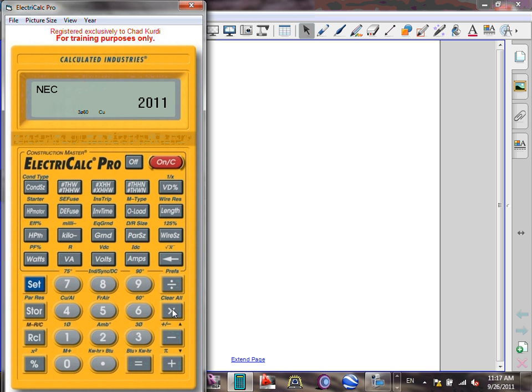Clear all. Clear all will default your calculator to the following: NEC 2011, 3-phase, 60 hertz, copper, 60 degree. That's clear all. So when you start changing later on, guys, as we move on, we start changing the ambient temperature and the derating and all this good stuff, and you have no idea, you're going to go back to the default. So clear all, set. Can you guys see set and clear all? That will get you back to the start point, which is 2011 3-phase copper 60 hertz.